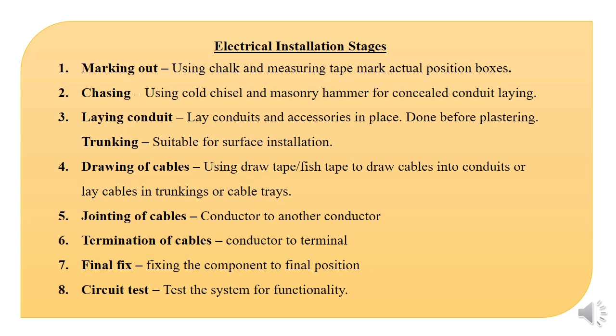After marking out, we do chasing. Chasing is necessary when doing concealed installation — for example, when conduits are installed inside the walls. For surface mount installations, chasing is not needed. After chasing, you lay the conduits in the trenches you made and hold them in place. Chasing and laying of conduits should be done before plastering if you're doing a concealed wiring system.